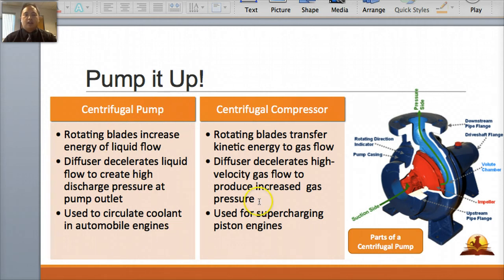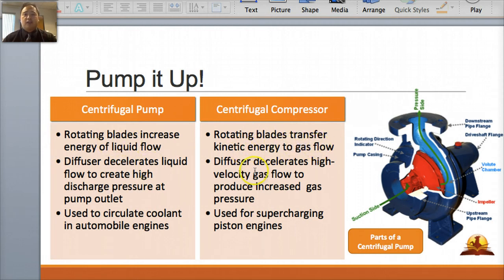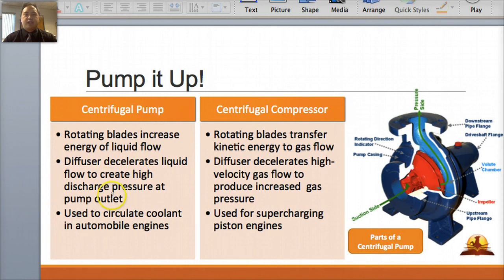The compressor — also known as a radial flow compressor — is similar to the centrifugal pump but is used more often to increase the pressure in gases. The rotating blades transfer kinetic energy to gas flow rather than liquid flow. The diffuser decelerates the gas flow to increase gas pressure. This is used for supercharging piston engines. So you can see how they're very similar: the pump is more for fluid and creates pressure that way, whereas a compressor does it for gas, which increases pressure. That's how a centrifugal compressor works.